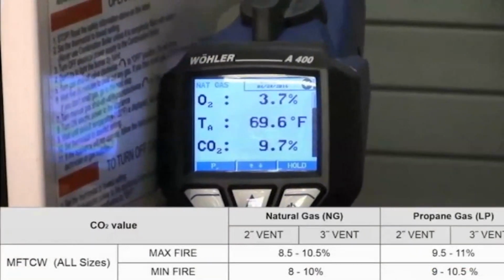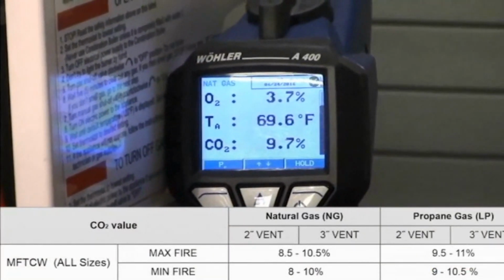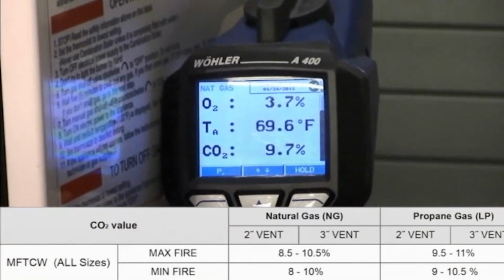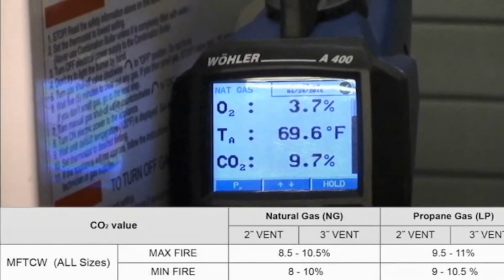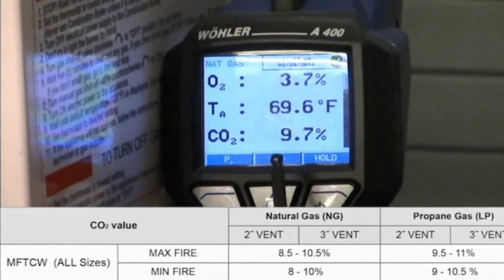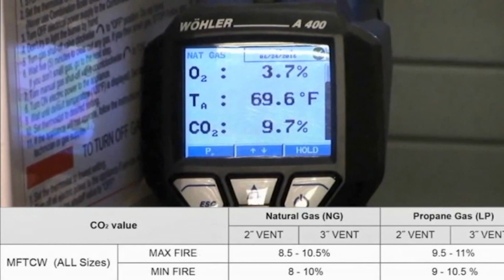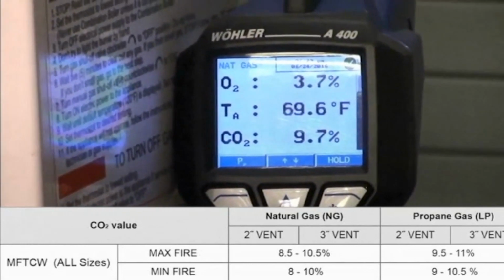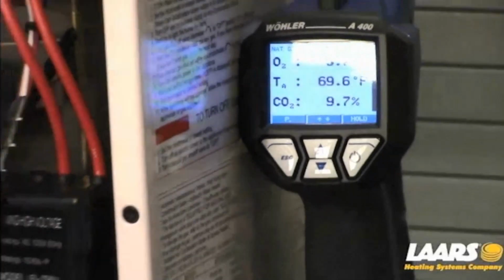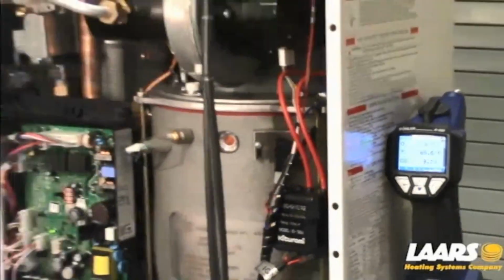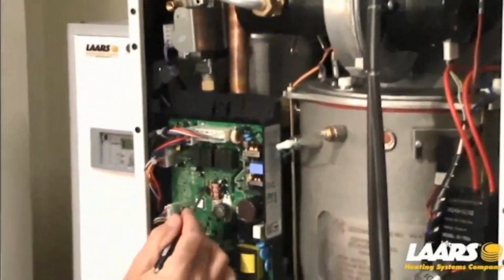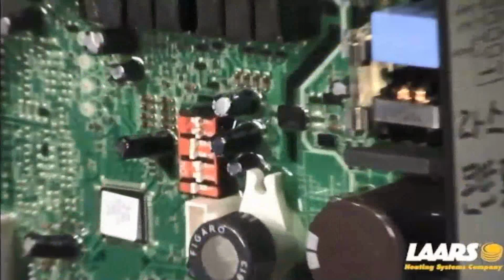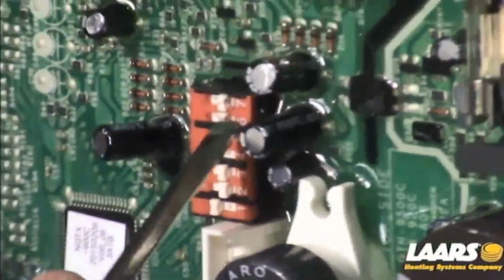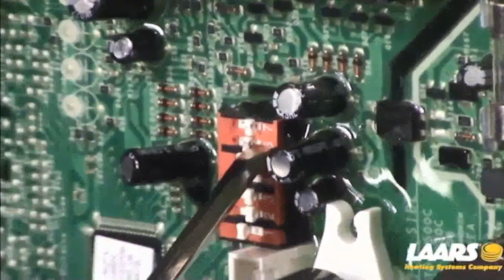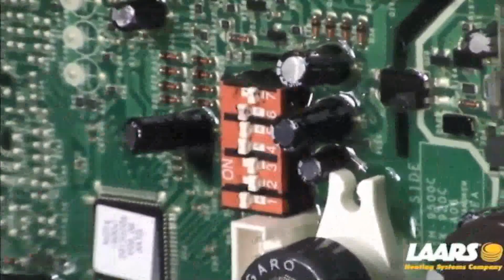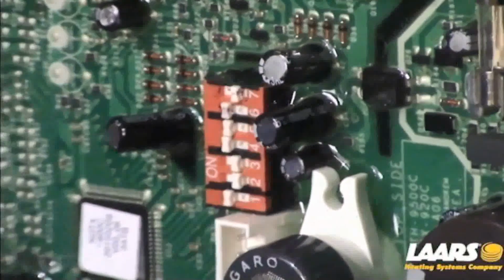As the chart will show you, min fire or low fire, that range is between 8 and 10% for natural gas. So as you can see, we're slightly below 10%, which is good. We're within range. We want to turn the boiler back to high fire. To do that, we go back to our dip switches. We turn dip switch 7 to the off position, which is the right-hand side. Dip switch 6 to the left-hand or on position, and allow that boiler to modulate to high fire.